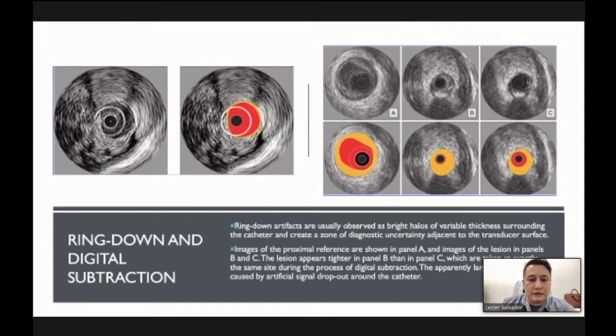Some programs like the time gain compensation or TGC can be used to decrease this artifact. Excessive ring down suppression can reduce the signal from targets close to the catheter, which is a downside. And another, on the right, is in electronic systems, where the transducers are surface mounted and ring down is partially reduced by digital subtraction of a reference mask. If it is incorrectly performed, subtraction has the potential to remove actual information or introduce a false border close to the transducer.